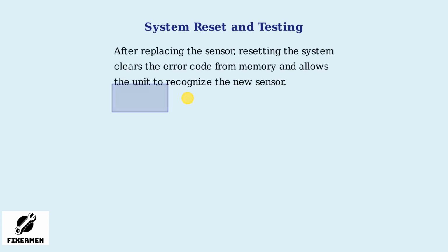After replacement, it's crucial to reset the system. This can usually be done via the thermostat or control board. Once reset, test the unit to ensure the error code is cleared and the system is functioning correctly. After replacing the outdoor coil temperature sensor, resetting the system is essential to clear error code 223 from the system's memory and allow the unit to recognize the new sensor.